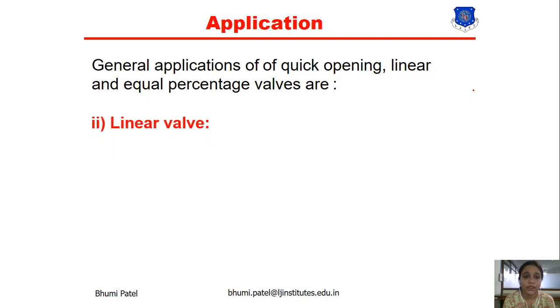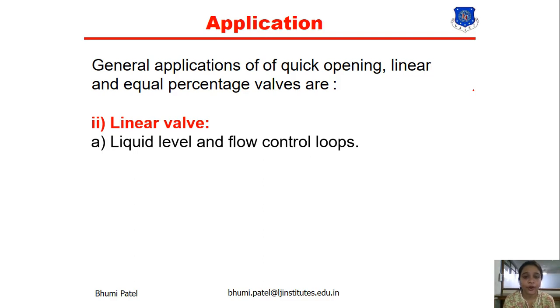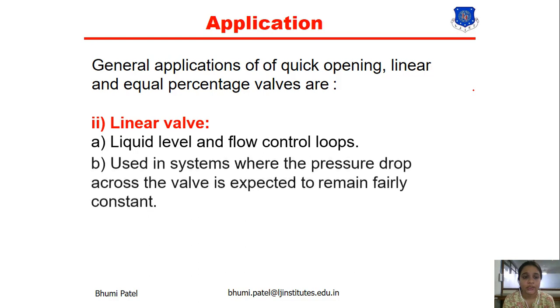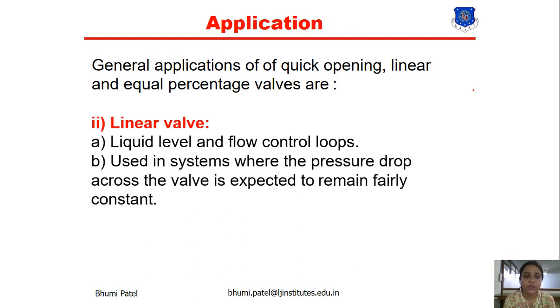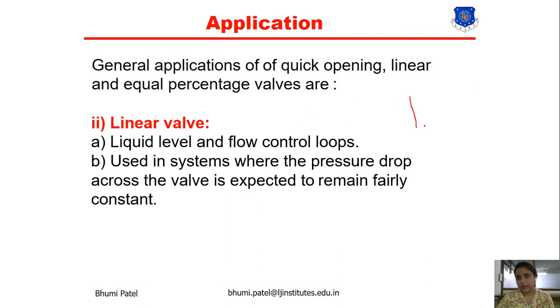The next application is for the linear valve. The linear valve is generally used for liquid level and flow control loops. It is also used in systems where the pressure drop across the valve is expected to remain fairly constant, because the graph of the linear characteristic is a straight line.